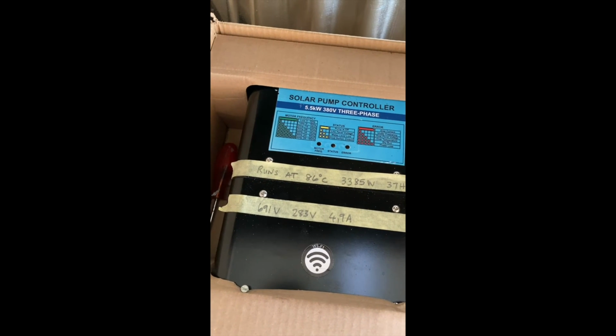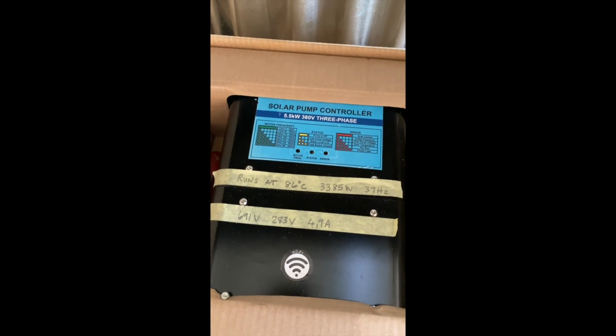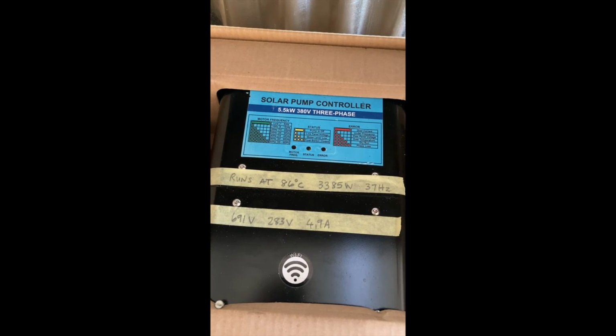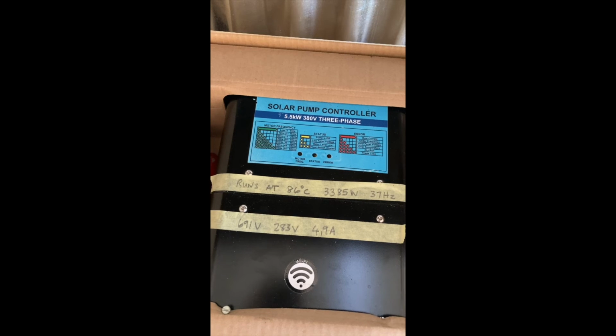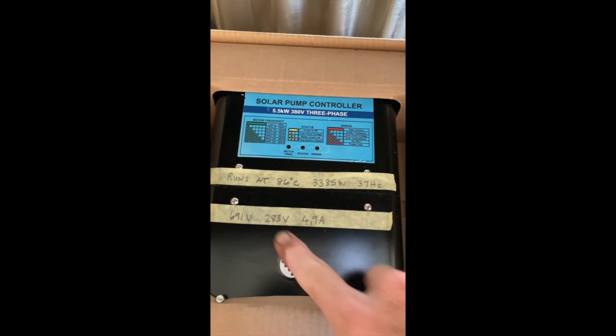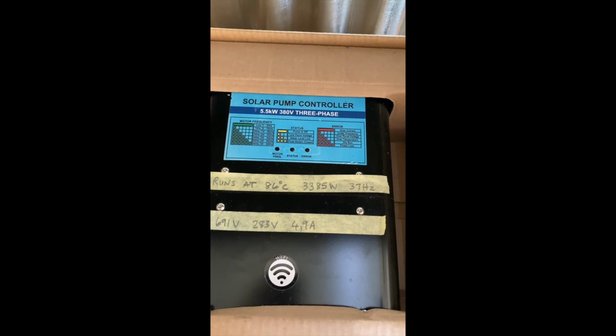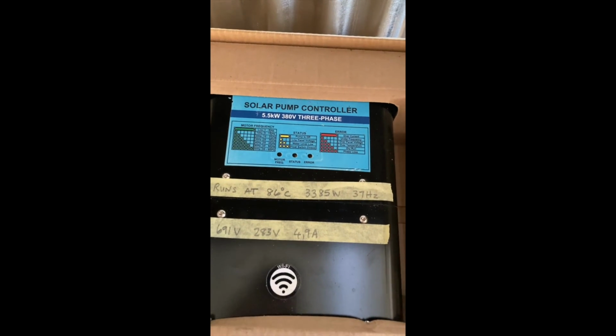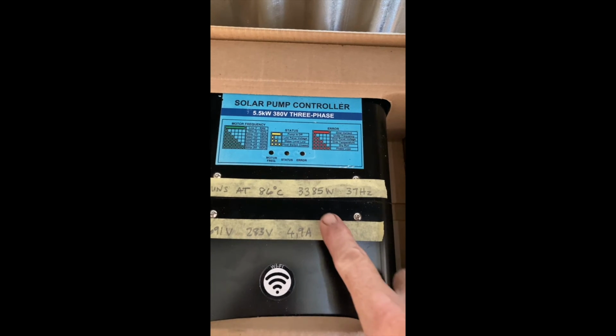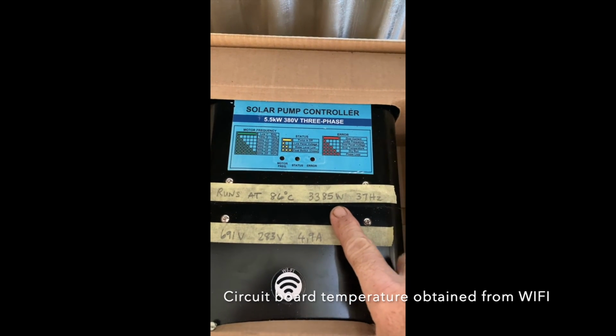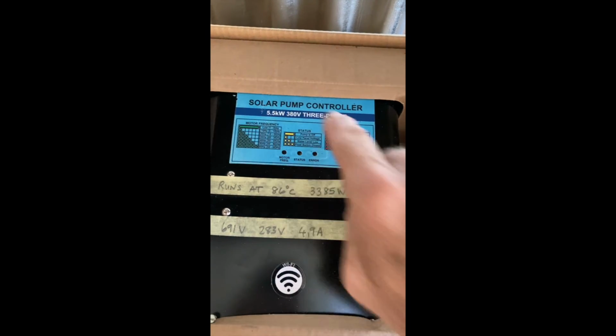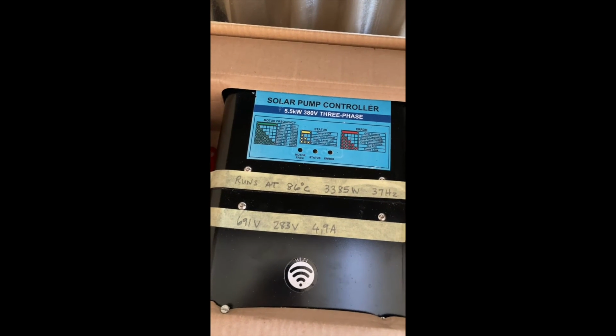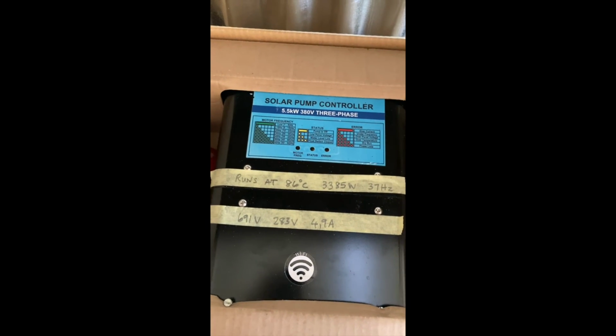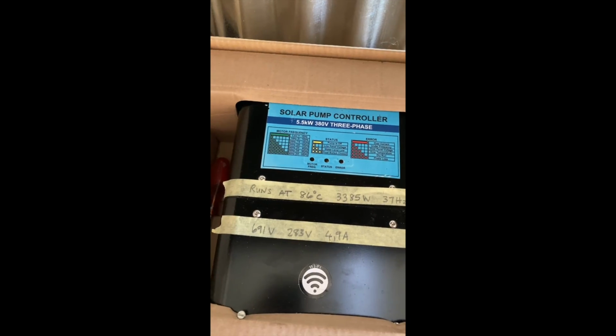Okay, so here's one of these microcare solar pump controllers. Damn fine piece of equipment, but if you use it in a really hot place like I do, you run into these problems. The unit cleverly powers down when things get hot, and mine, for example, at 86 degrees C drops right down to 3385 watts, where it's actually a 5.5 kilowatt solar pump controller. So I came up with a hack to solve that problem.